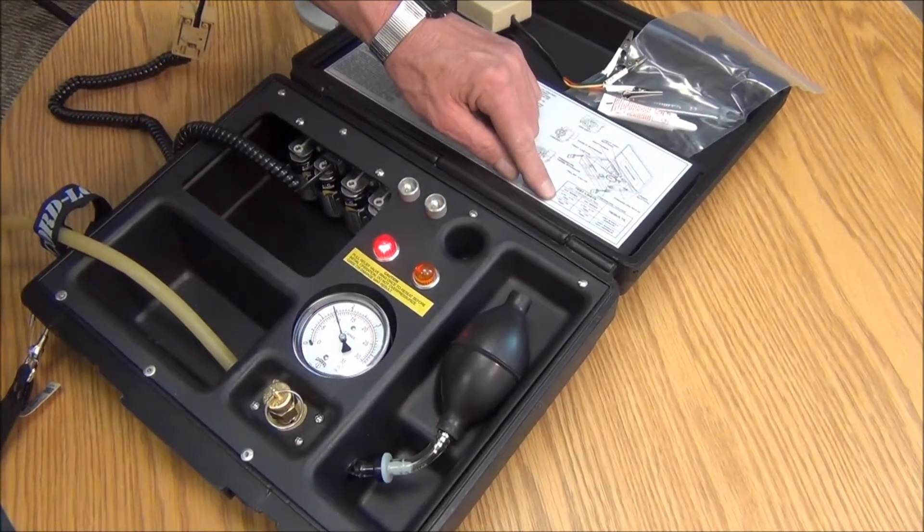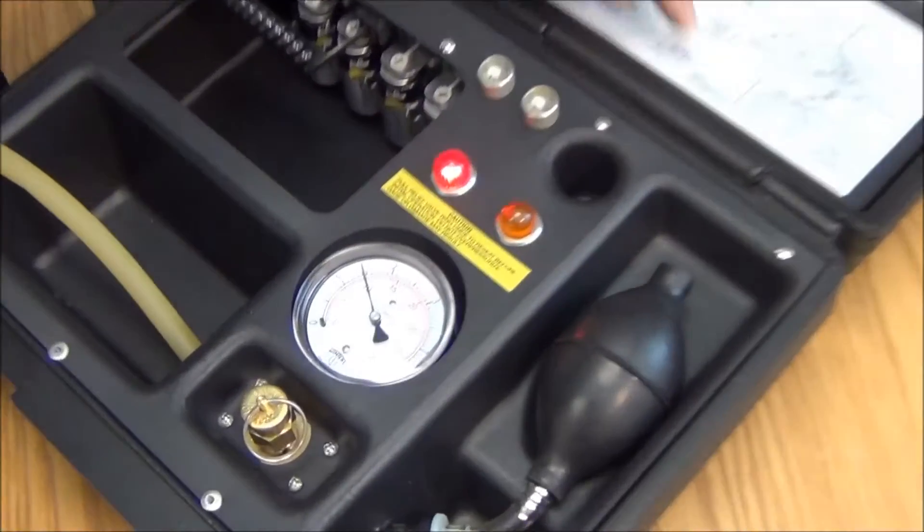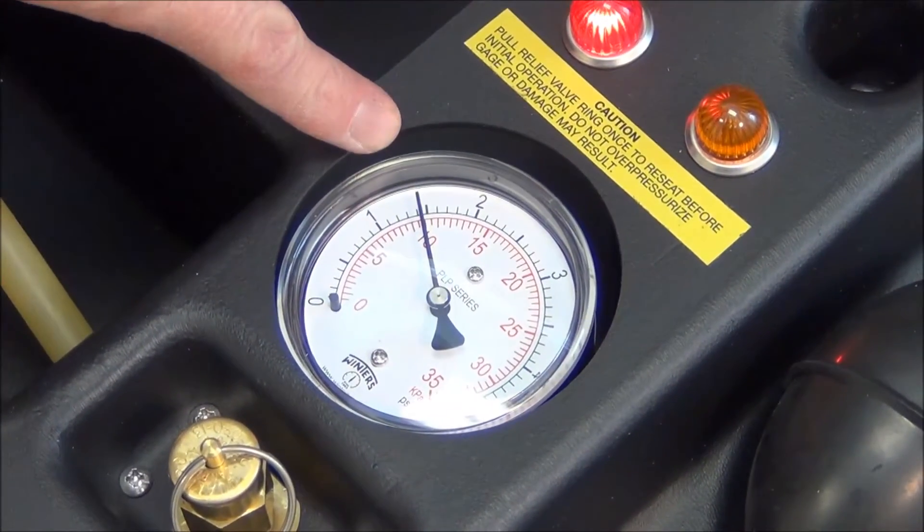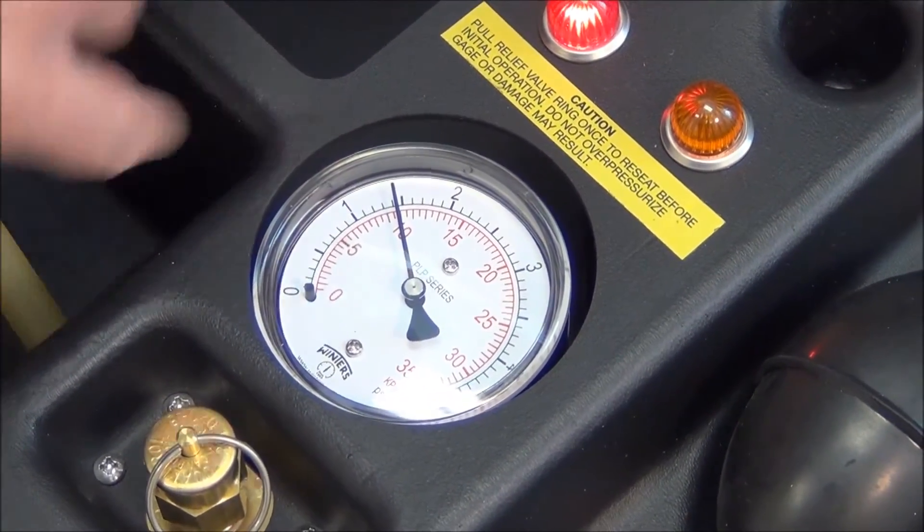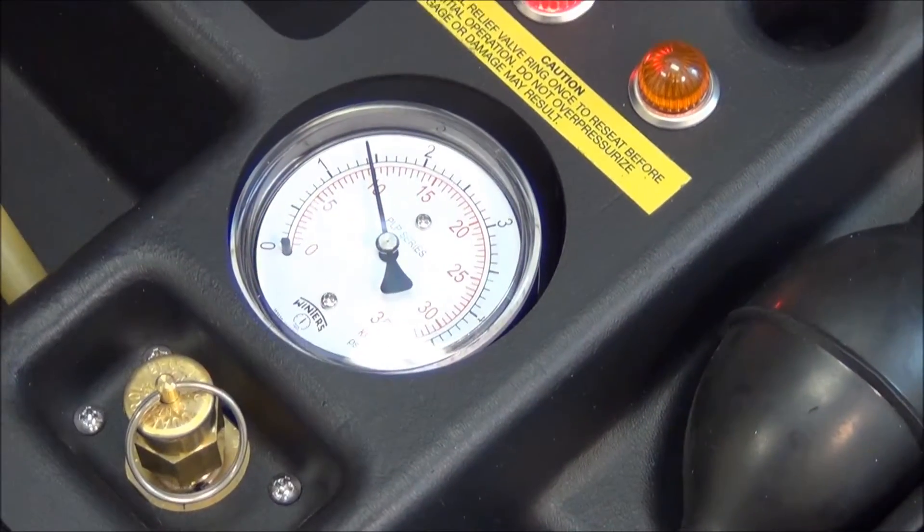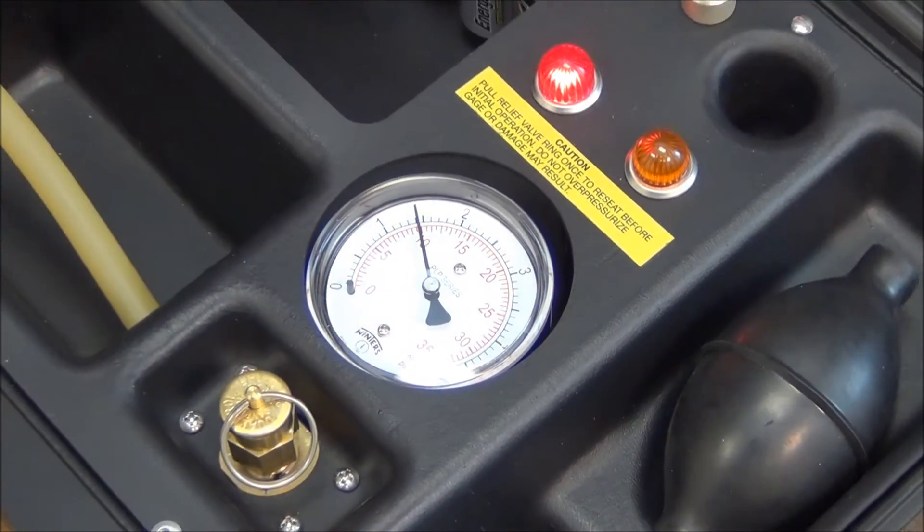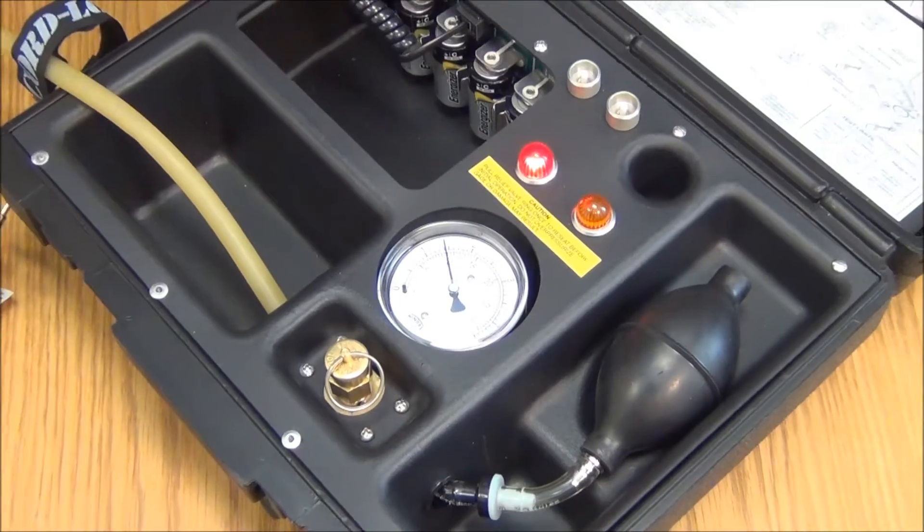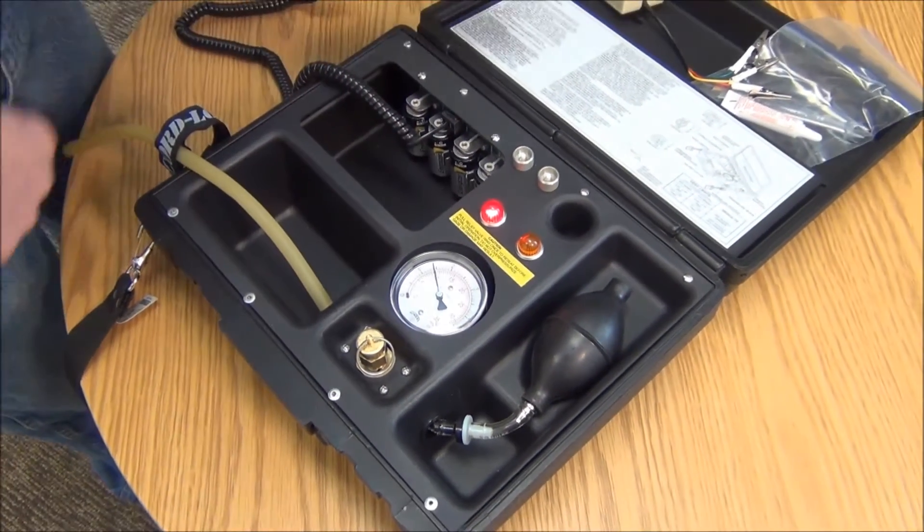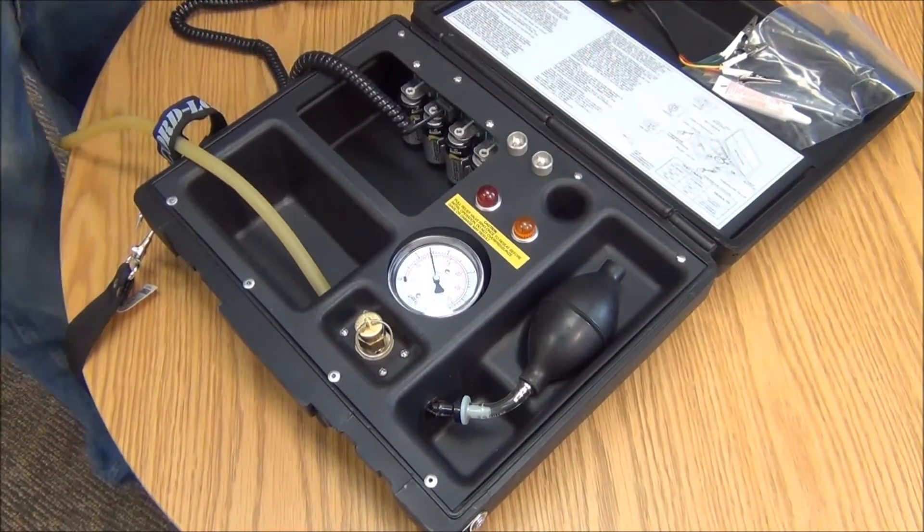I'm a little under 1.5 PSI and the needle looks like it's stabilized. If you start losing pressure, check these fittings to make sure everything's connected good. Typically this bushing might have to be tightened down. It looks like I'm holding pressure just fine, so I'm going to reset the timer.